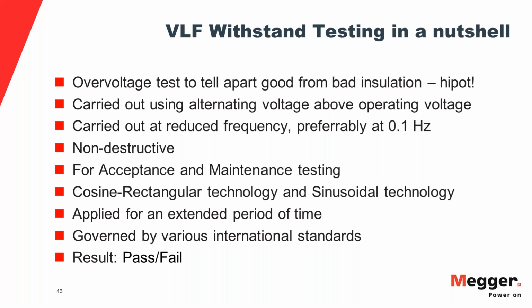So if you switch on, nothing will explode. If you pass a VLF test, it's kind of a safety test. Will it find all the defects? Obviously not, because some of these defects, specifically in the accessories, sometimes take months and years to grow. That's something for the PD, which the PD diagnostics will make visible. But if you have very severe workmanship issues, then this will fail during the VLF withstand as well.